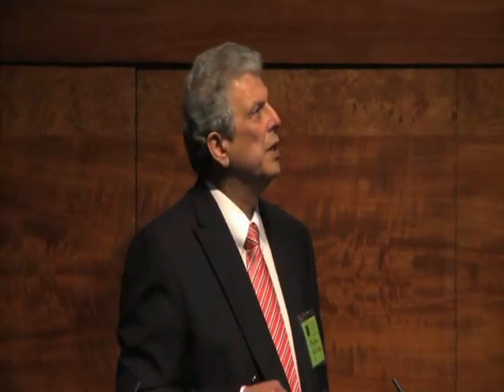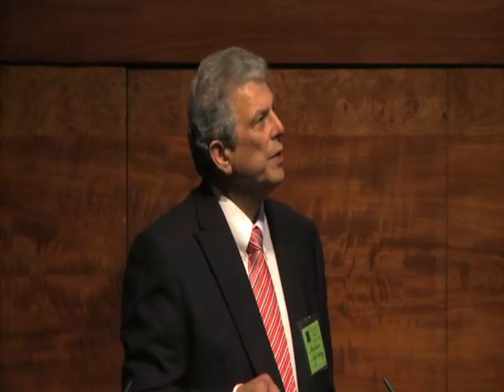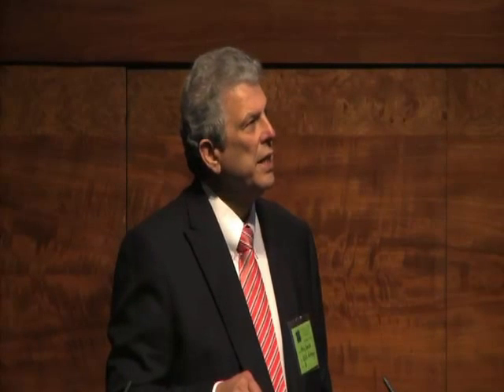Now, quickly, the sustainability. As I showed you earlier, we did a first circulation, and then that wasn't accepted. We went deeper, and we did another one. So in concept, if you have 3 systems like that, 1, 2, and 3, you can run one system for 25 years. That drops by 10 degrees. Then you go down and use the next system for another 25 years. Then the third system. And the calculations show that it takes 75 years to recover the 10 degrees. So in principle, you can go up and down forever. The heat through conduction will make this sustainable forever. You don't need to worry about it. I'm not sure about the engineering problems, like casing, but it is possible to make it perpetual.